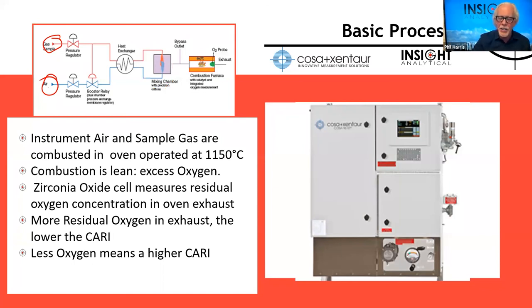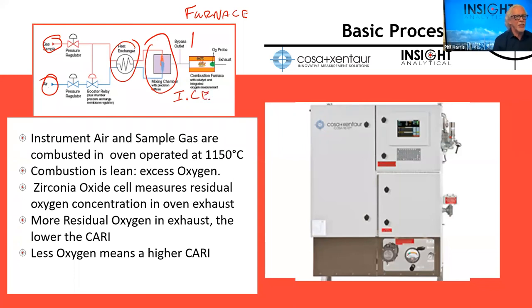Oops, I don't show the static mixer over here. In this case, they show a heat exchanger, but that's where I get all this mixing going on. Actually, here's the mixing chamber right here. So my intake manifold is this static mixer. Mix the air and the fuel, get them really well mixed, and then put it into the engine and burn it. That's what happens in the furnace, right? So the furnace in this analyzer is my internal combustion engine. It burns the fuel oxygen mixture. And then we have an oxygen sensor at the backside to say, how well did you do on the burn? And can I tune the engine up a little bit and adjust your air to fuel ratio a bit?